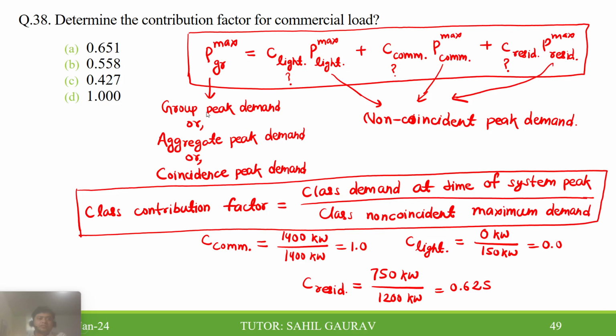So here I have written it in a better way. Here it is P_GR max, that is group peak demand, and it is also called aggregate peak demand. It is also called coincidence peak demand, and these are the non-coincidence peak demands, meaning individual peak demands. So in this problem you have to find the contribution factor of commercial load.